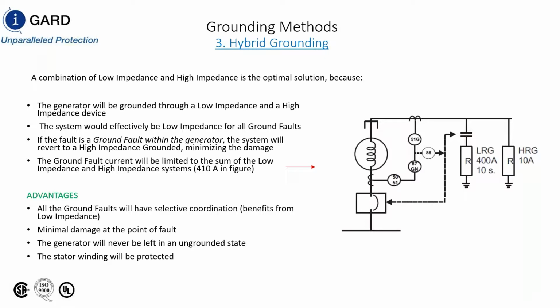I can see if I can find the reference and I'll send it out to you. But yes, in low resistance or medium or high resistance grounding systems, CSA allows a 14 gauge wire to be used for a 10 amp resistor. NEC states that you have to use a minimum number 6 copper or number 8 aluminum wire for a high resistance grounding system, but there's no help in low resistance grounding system. So I will send you that formula that you can use for that.